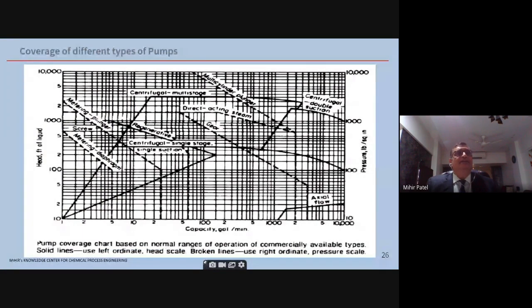As you can see, the capacity is on the x-axis and the head is on the y-axis. So when the capacity is low, you enter into the metering category, which is the positive displacement pumps. On the right-hand side, you see the axial flow pumps with a very high capacity and low head. These are very high capacity pumps, but the heads are very low. So this is the overall nomenclature of the pumps.